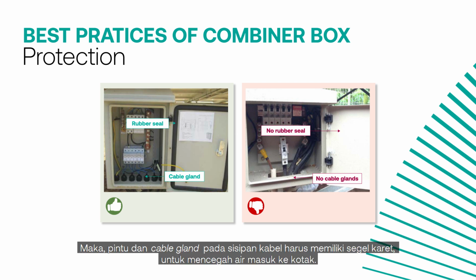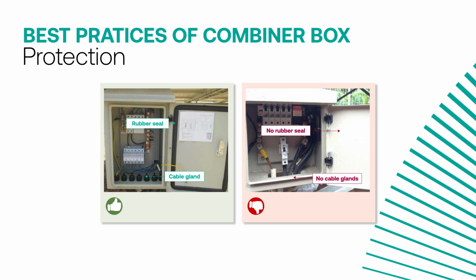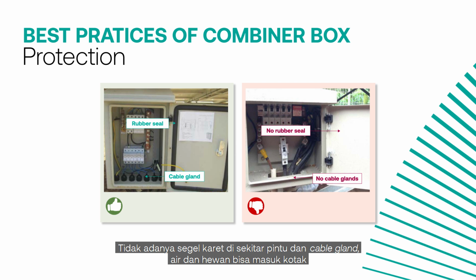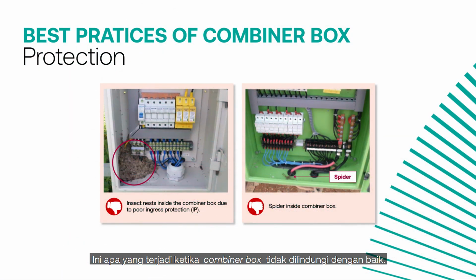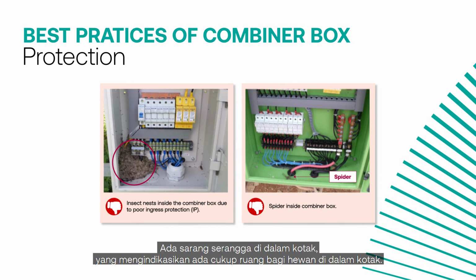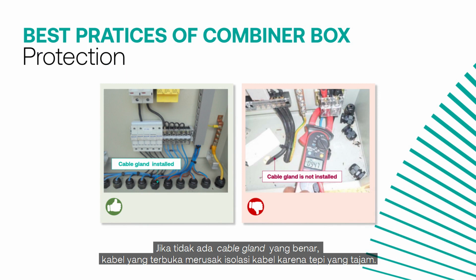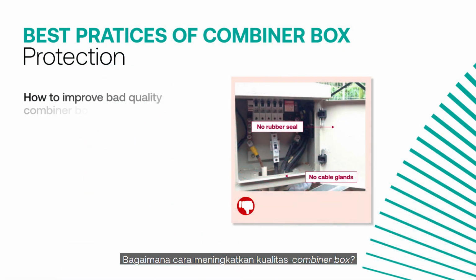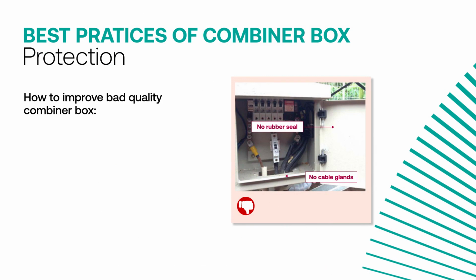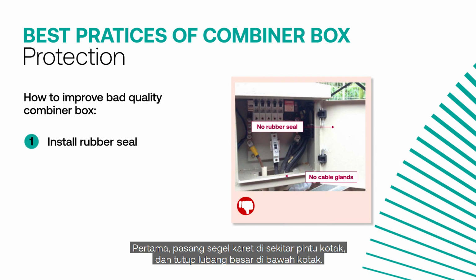To achieve this, the door should have a rubber seal and cable glands at the cable insertions to avoid water entering the box. Absence of a rubber seal around the door and cable glands will allow water and animals to enter the box. This is what happens when a combiner box is poorly protected. There is an insect nest inside the box that indicates there is enough space for animals to enter the combiner box. In the absence of a proper cable gland, cables will be exposed to the sharp edge of the enclosure that can damage the cable insulation. How to improve the quality of a bad combiner box? First, install a rubber seal around the door and close the big hole at the bottom of the box.